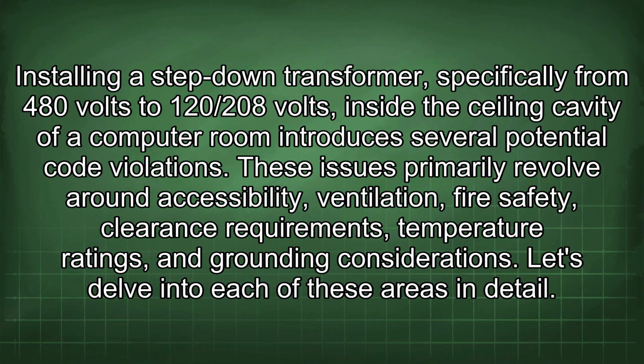Installing a step-down transformer, specifically from 480 volts to 120/208 volts, inside the ceiling cavity of a computer room introduces several potential code violations. These issues primarily revolve around accessibility, ventilation, fire safety, clearance requirements, temperature ratings, and grounding considerations. Let's delve into each of these areas in detail.